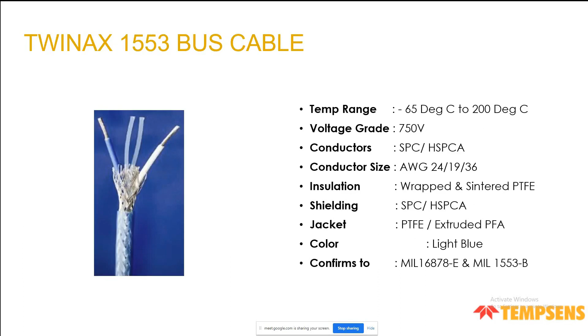Then Twinax cable, bus cable, underwater cable, which has special insulation. Then linear heat sensing cable, which is a twisted pair cable. It is useful to know where a fault has occurred because of high temperature. It will sense the heat, and they are available for 68 degrees, 78 degrees, up to 180 degrees. The cable would make a connection if it sees high temperature, and there would be an alarm available to the customer.